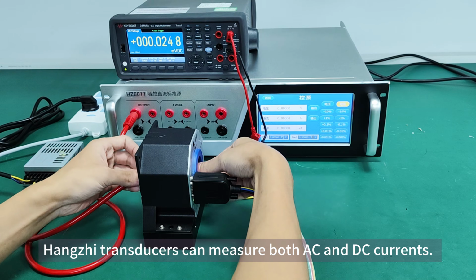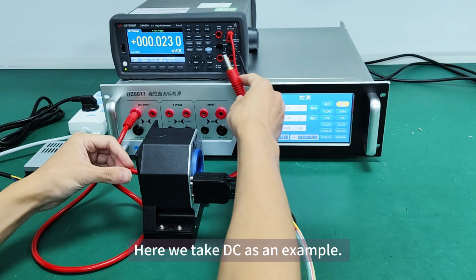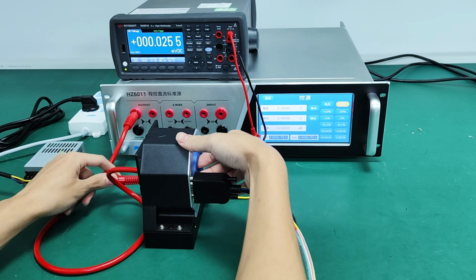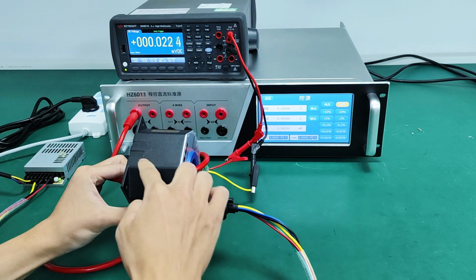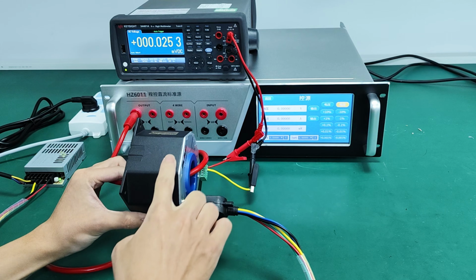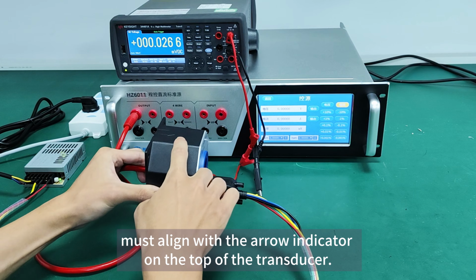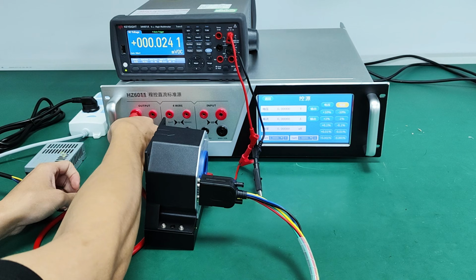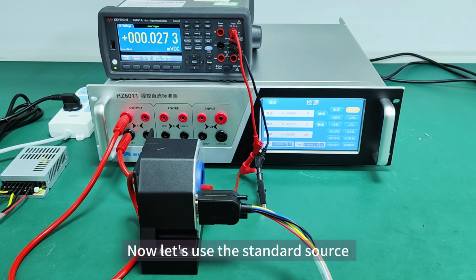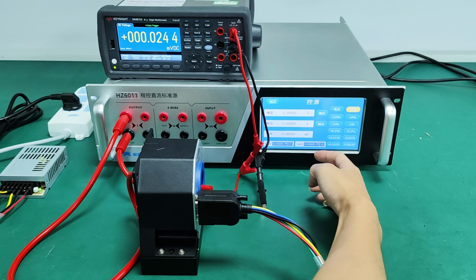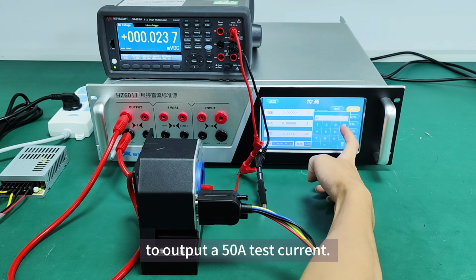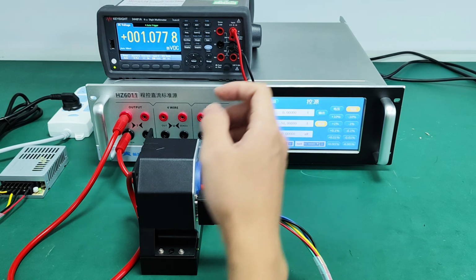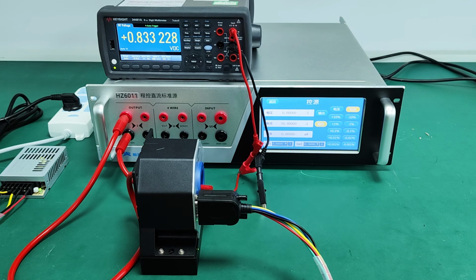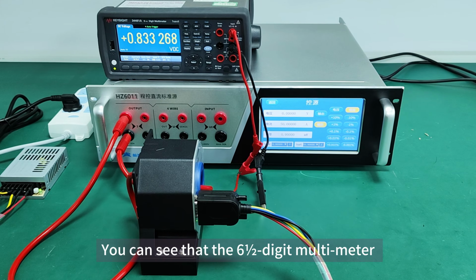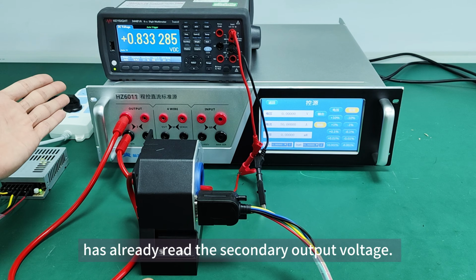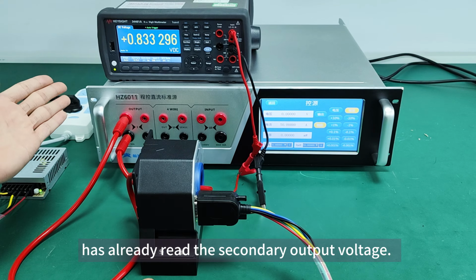Hangzhi transducers can measure both AC and DC currents. Here we take DC as an example. When testing DC, the positive current direction must align with the arrow indicator on the top of the transducer. Now let's use the standard source to output a 50A test current. You can see that the 6-digit multimeter has already read the secondary output voltage.